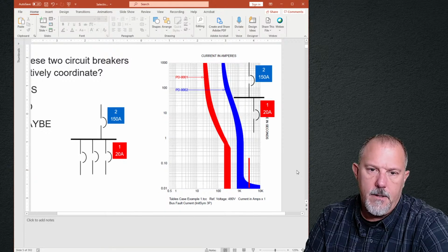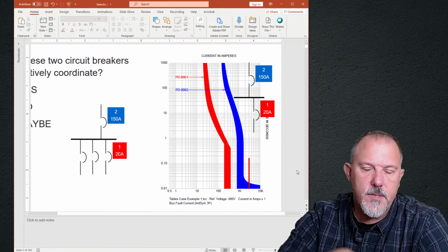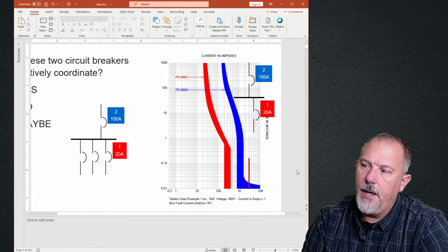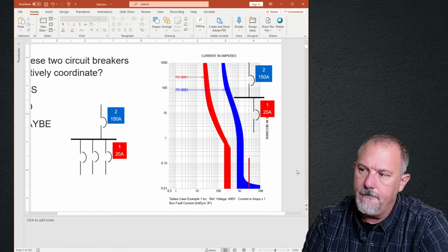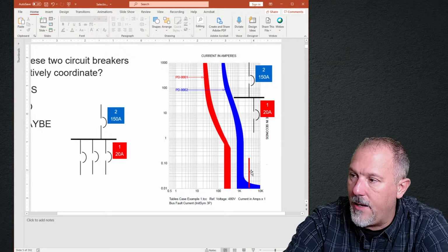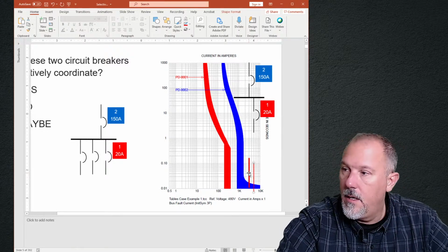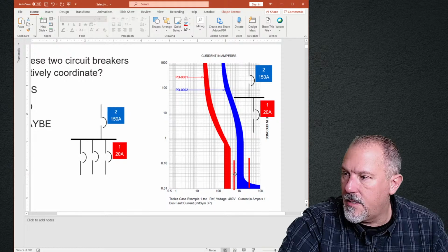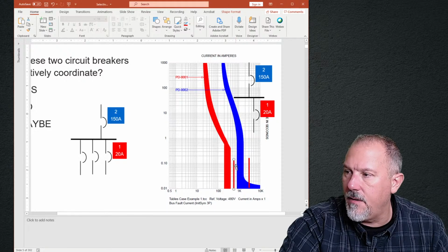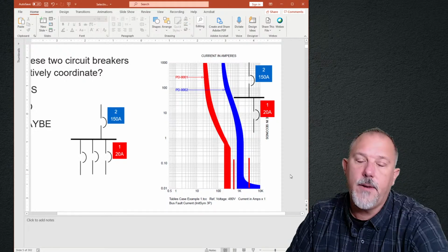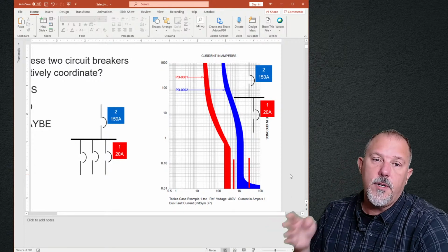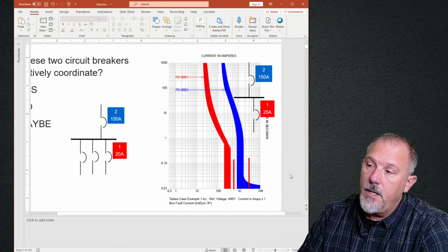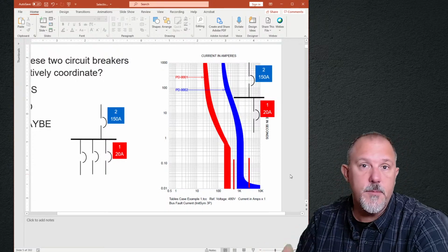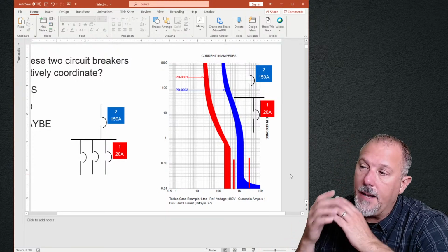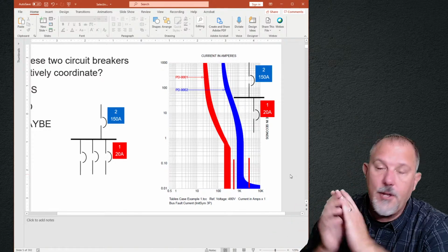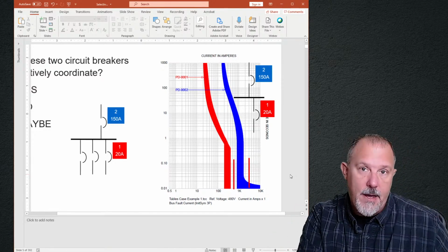And I would go to the customer and I would say, okay, look, you don't selectively coordinate to the bolted fault current value. I would also plot a lower value and say this is the, I don't know, the arcing ground fault current. I would say, okay, you don't selectively coordinate to the three-phase bolted fault current value, but the most common fault in a power distribution system is the arcing ground fault. So I plotted that value and you coordinate to that value.